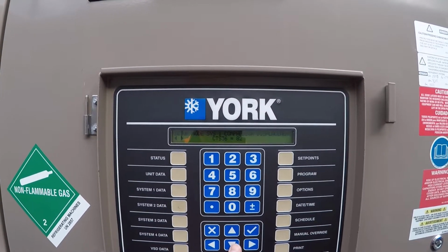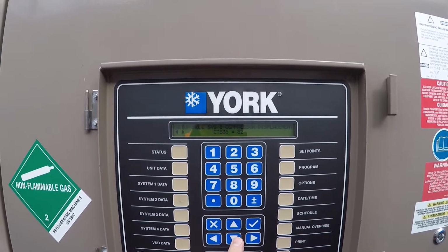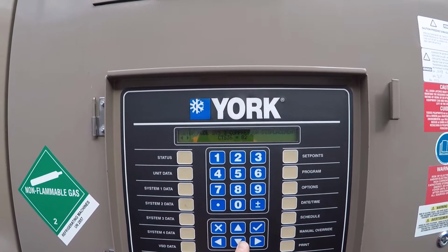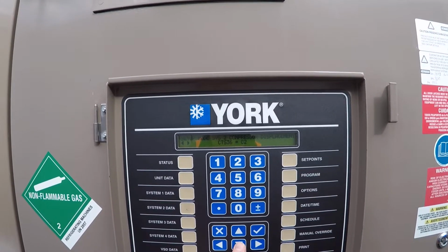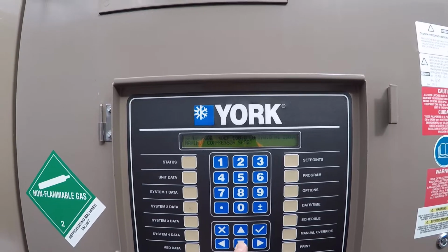Condenser fan control. You can actually have OPT stage. So there's different types of fan control. You can have VSD fan control and the like. This is also where you select what compressors you're driving. Because sometimes these big units come with 2 different size compressors, and you got to make sure they have the correct compressor selected.